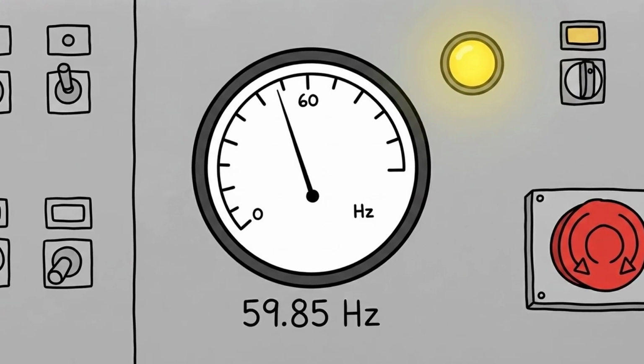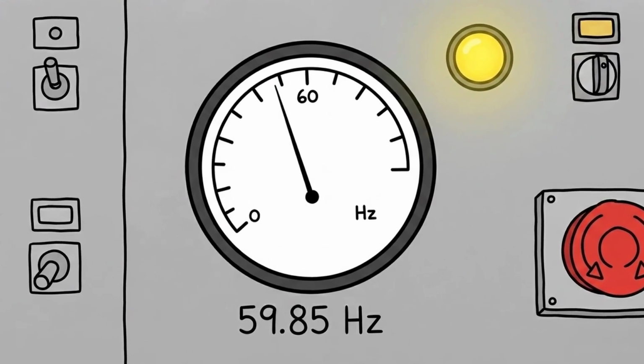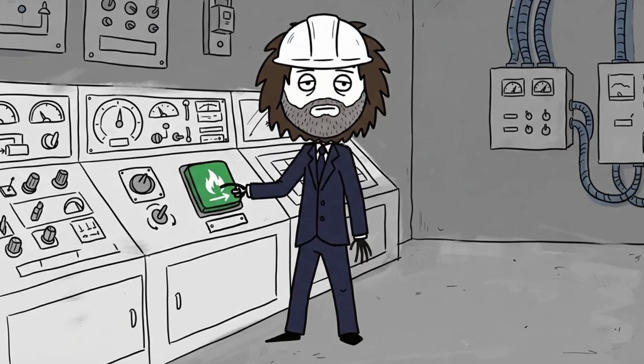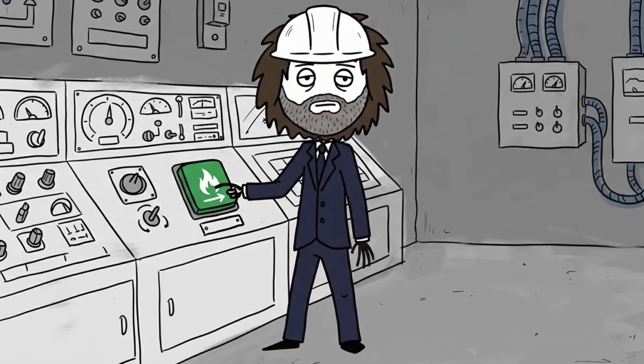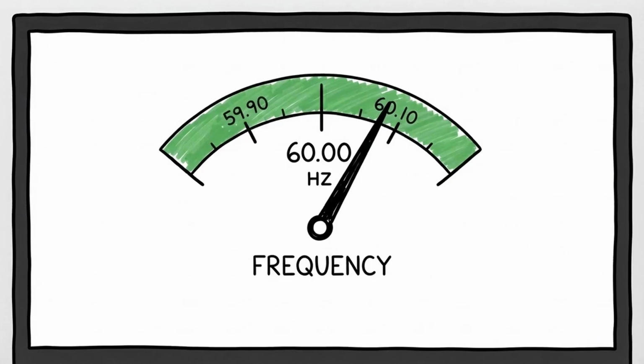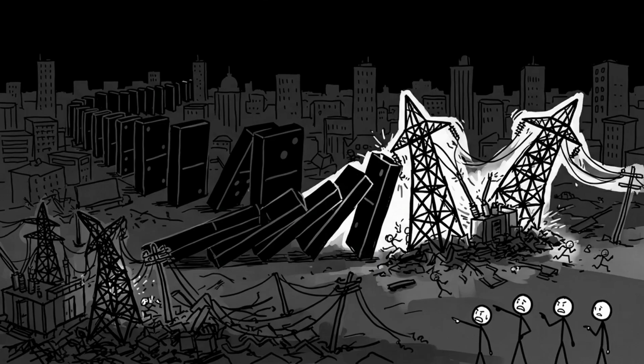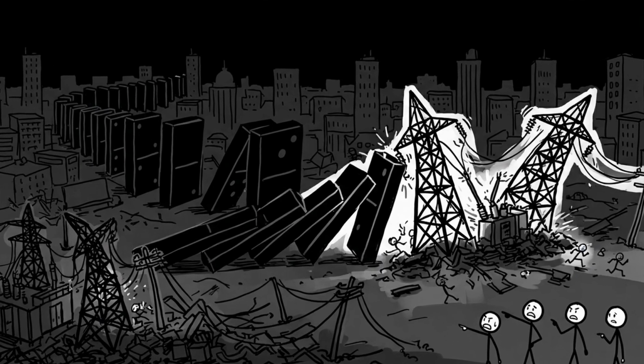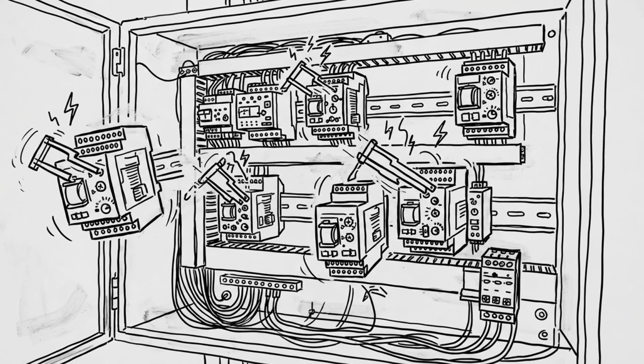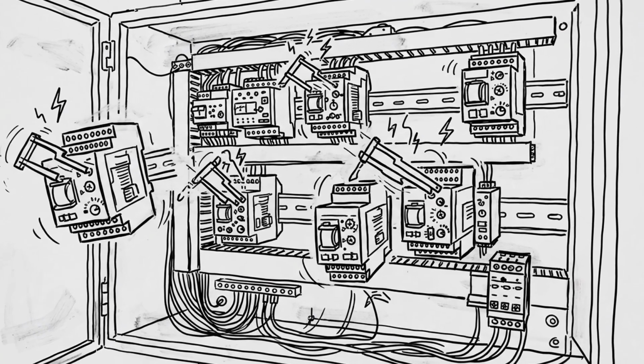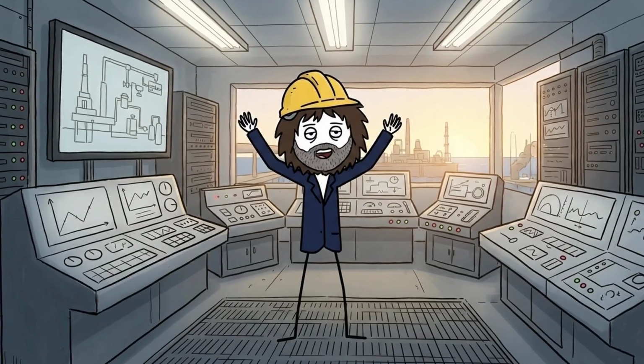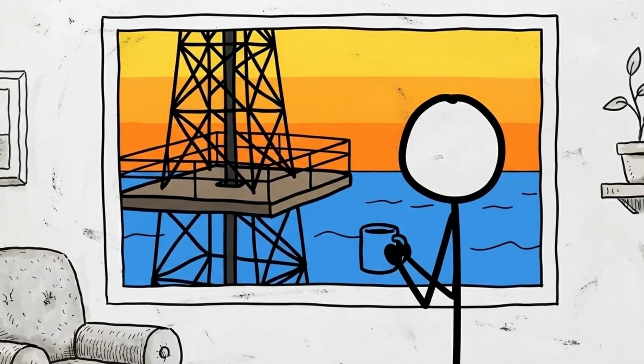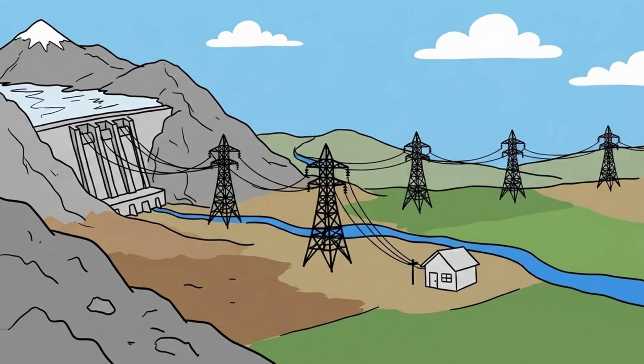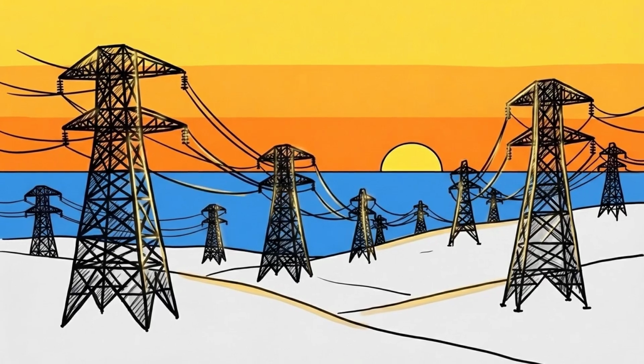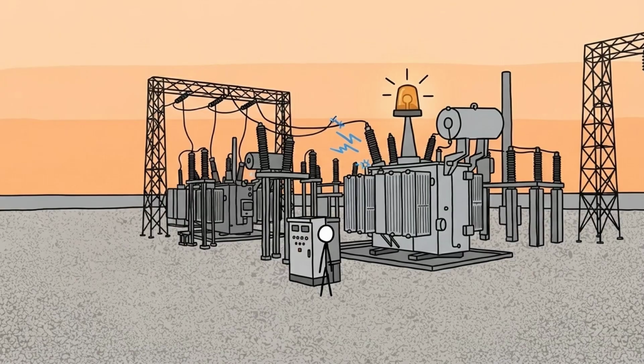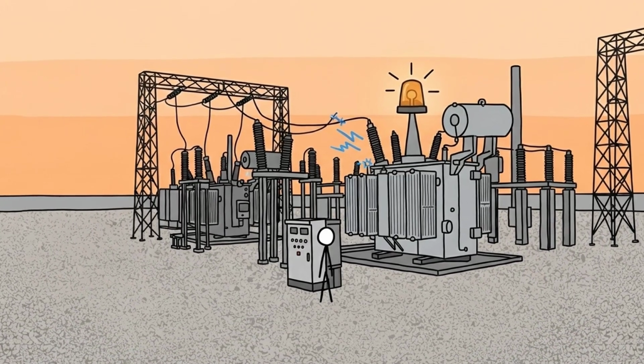Power grid operators must constantly balance total electricity generation with total consumer demand to keep the entire system vibrating at precisely 60 cycles per second, or 60 hertz. If millions of people turn on their appliances simultaneously and power plants cannot ramp up production fast enough, the increased electrical drag physically slows down the massive steel turbines at the generating stations, causing the grid frequency to drop. If that frequency falls by even a fraction of a single hertz, automatic safety relays across the country will instantly begin shedding entire cities from the grid in cascading blackouts to prevent multi-million-dollar generators from ripping themselves apart.